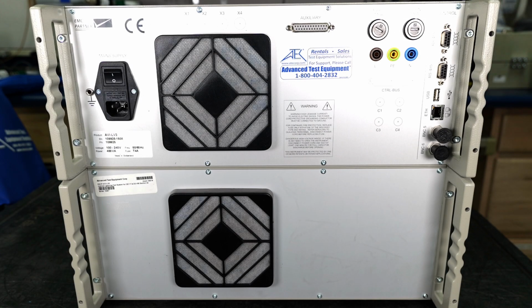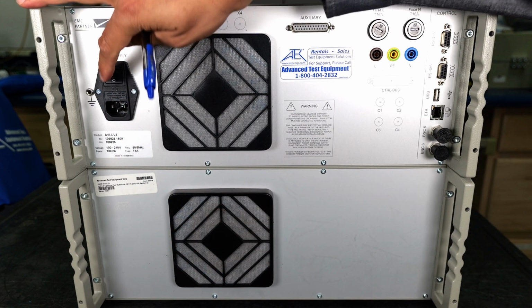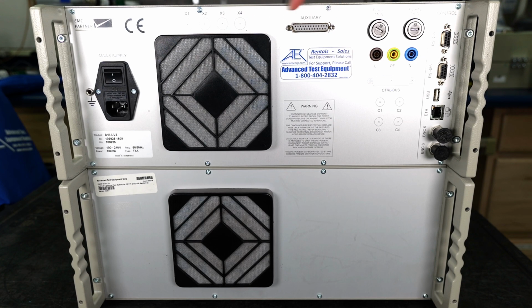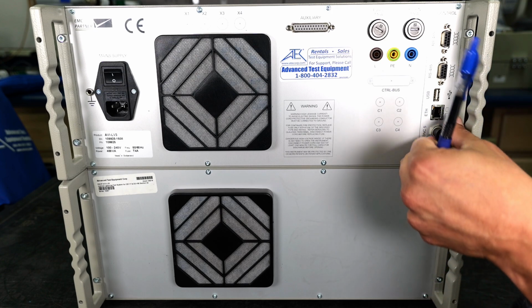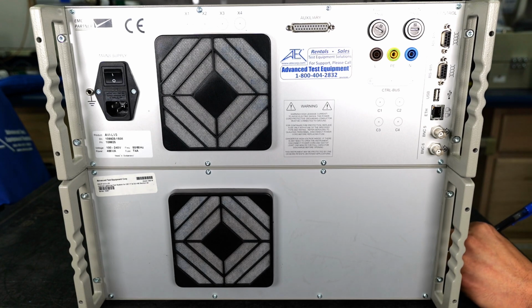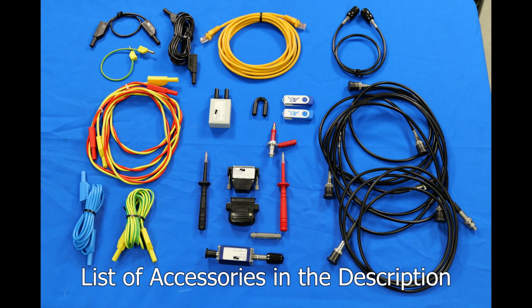Now we're going to take a look at the rear panel. You're going to have the AC input, which is 100 to 240 volt single phase, an on-off switch, obviously your fans. The interlock connector actually plugs in here, or you could wire an external warning light. And then you have a line, ground, and neutral input connection. And then you're going to have your communication ports, RS-485, USB, Ethernet, and then 2 more BNC inputs and outputs that you could program using the front panel. And with each AVI-LV3, we include the standard set of accessories, which has that BT7 Injection Transformer, as well as several verification cables, accessories, and shunts.